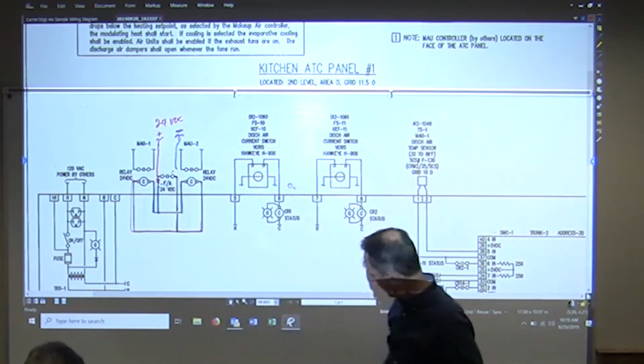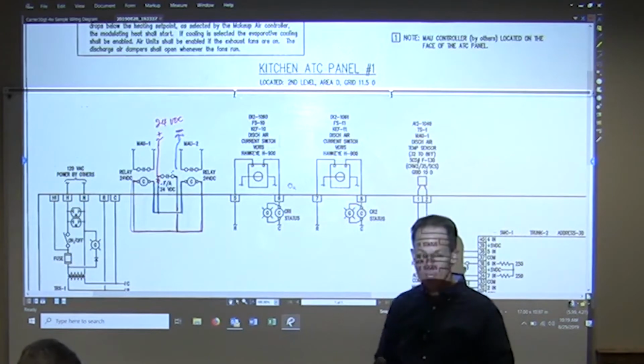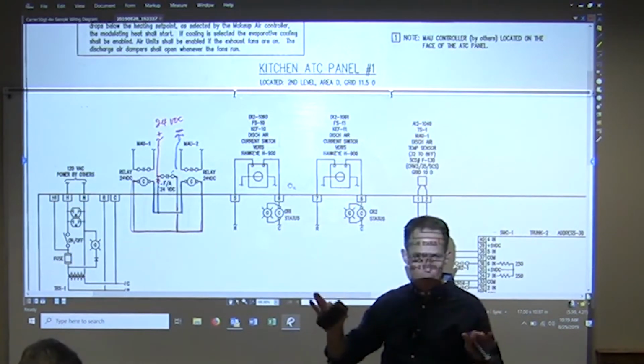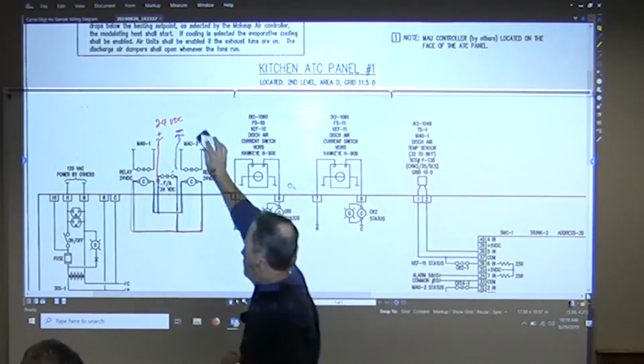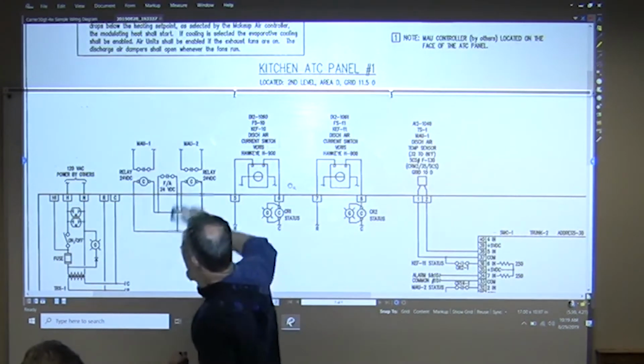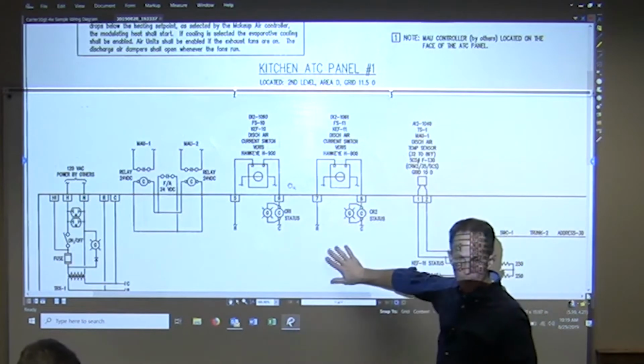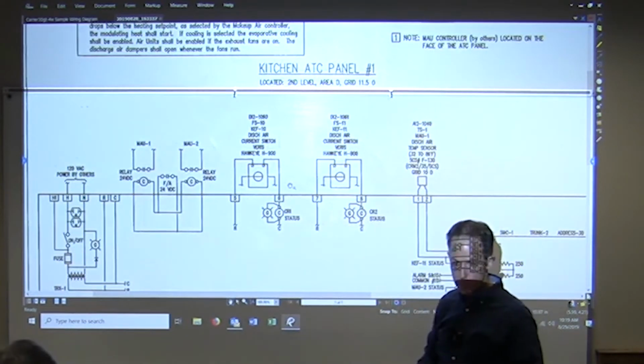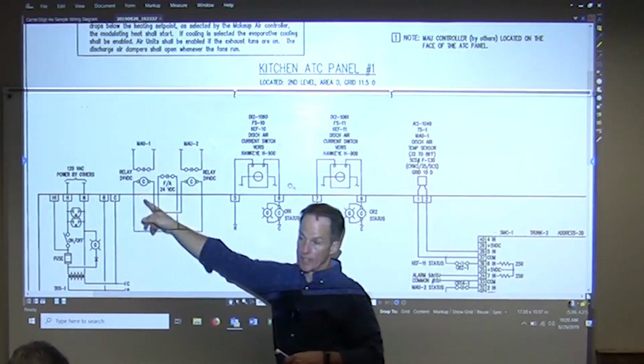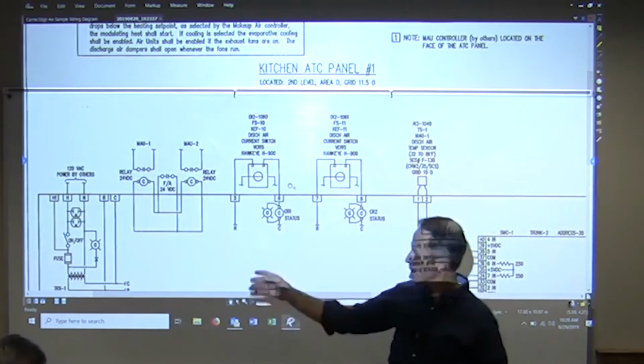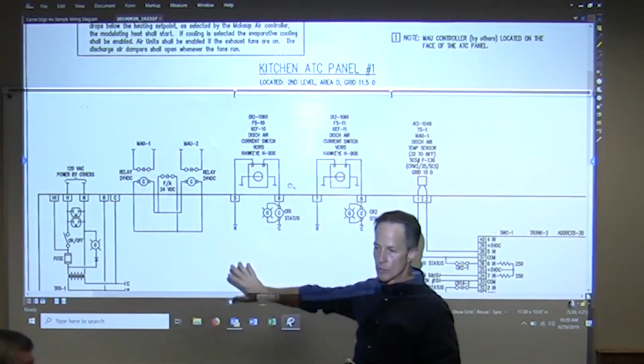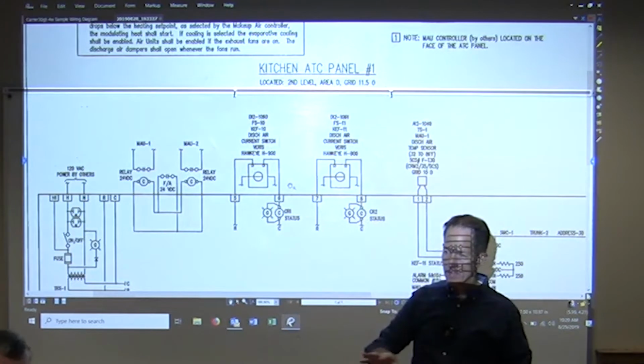Say, for instance, I decide I don't want to use the DC because the fire alarm system won't let me borrow their power. How would I fix that? Using our panel power. Full bridge rectifier in there and bring it in. Change out the relays. Okay, so we could change these relays, maybe instead of a rectifier. You could do 24 in here, but we don't have it. So using what we have, maybe easier would be change out the relays to a 24 volt AC.